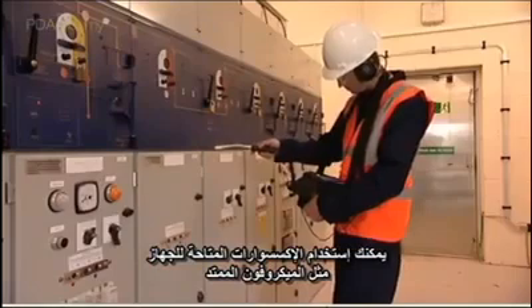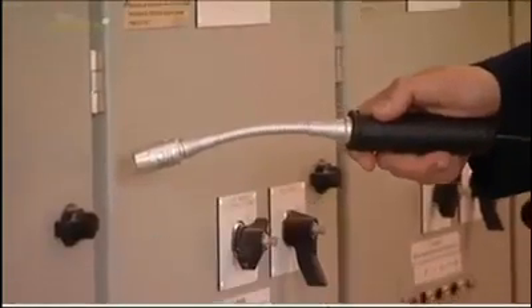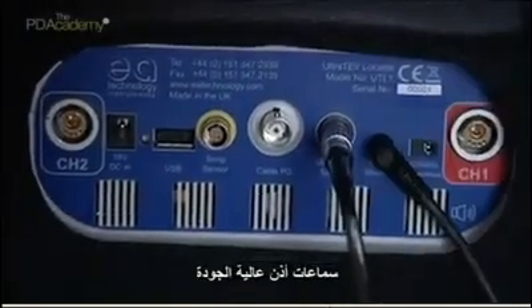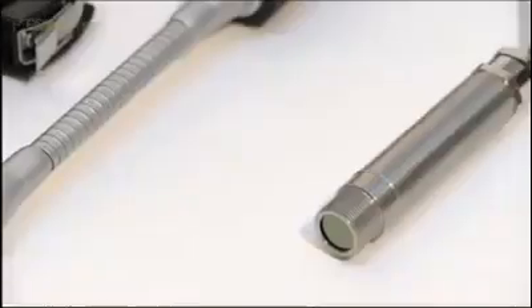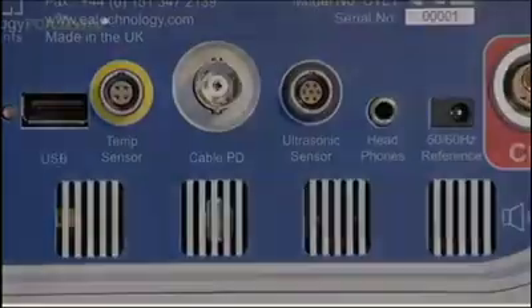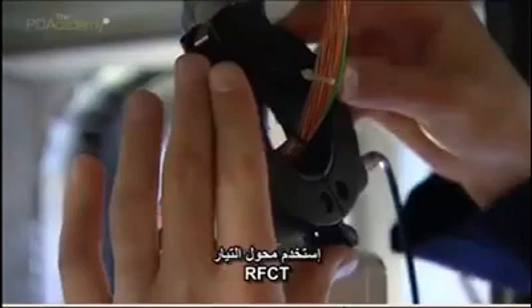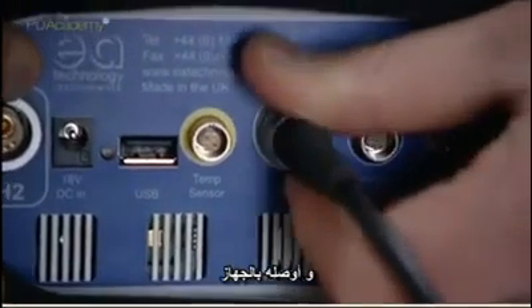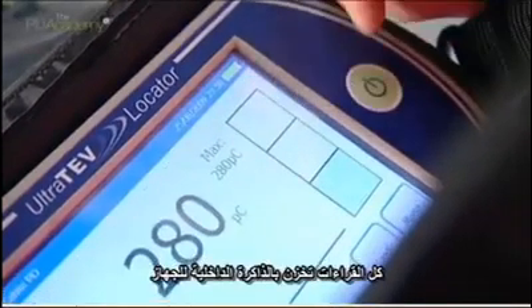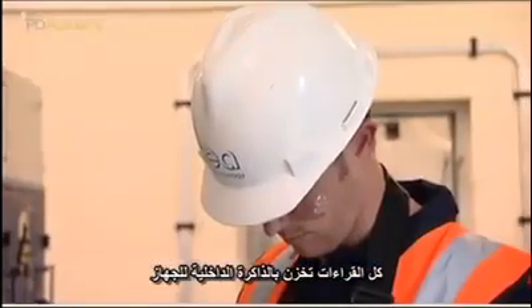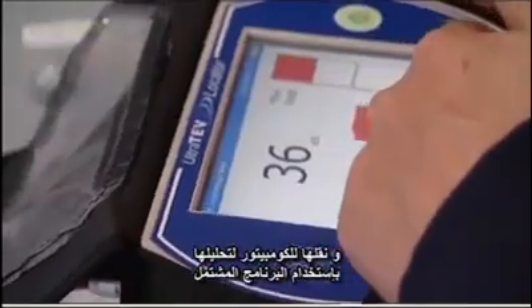For more detailed surveys, use the system's full range of sensor attachments and accessories, including the extension microphone, high-quality headphones, directional microphone, spot and ambient temperature sensor, pressure and humidity sensors. For measuring PD activity in cables, simply clip on the RFCT sensor and plug it into the central unit. All of the data you collect is stored in the unit's internal memory, where it can be accessed via the touchscreen menu and transferred to a PC for analysis with the software included.